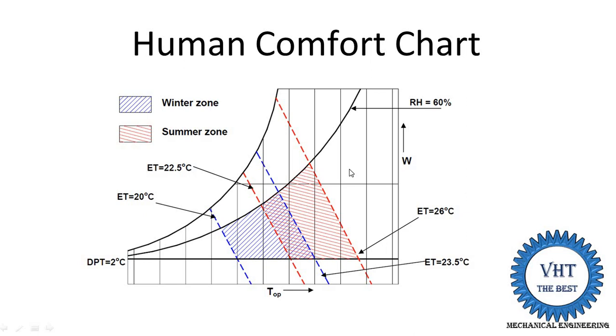Now for the winter zone: 90% of people feel comfortable at an effective temperature of 20 degrees centigrade. This blue line indicates the effective temperature of 20 degrees centigrade. Another 10% of people feel comfortable between 20 degrees centigrade and 23.5 degrees centigrade, which is another blue line at 23.5 degrees centigrade.